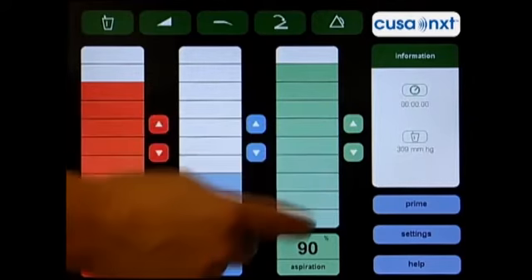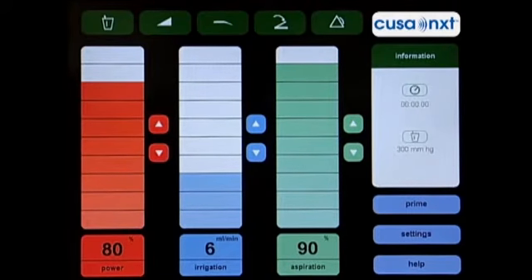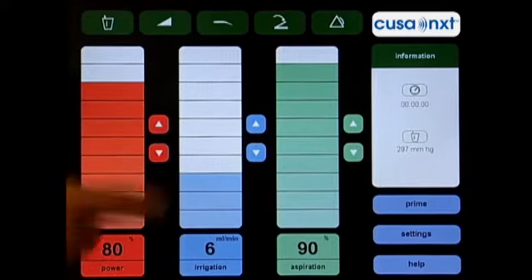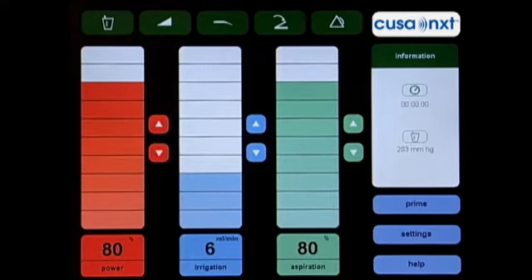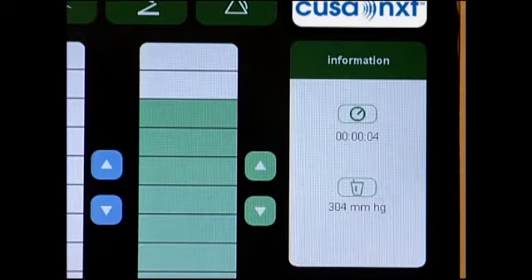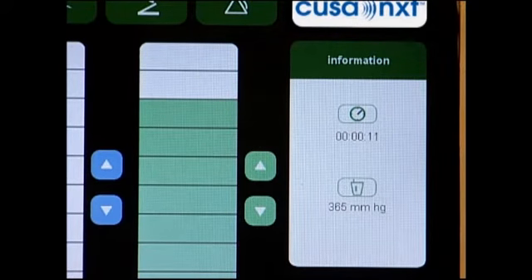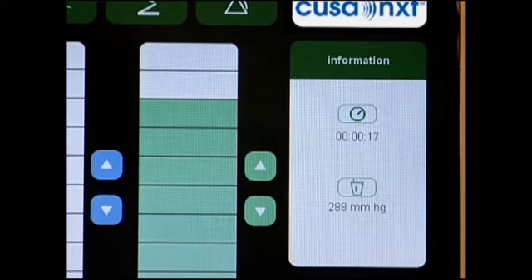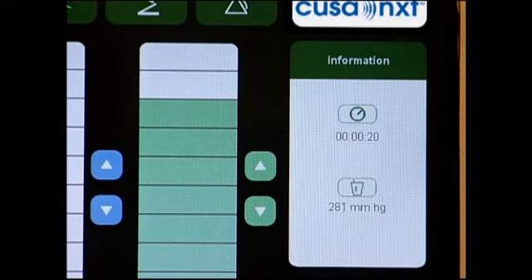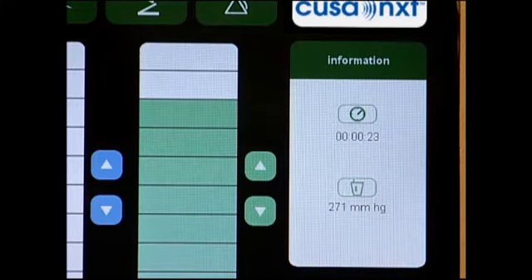To adjust the aspiration level, press the appropriate green arrows or indicator bar. Each touch of an arrow will increase or decrease suction power 5%. Touching the aspiration scale will increase or decrease the setting by 10%. Typical aspiration settings are between 70% and 100%. During system operation, the information panel will display the cumulative handpiece activation time and the actual suction power, measured in millimeters of mercury. Should the surgeon wish to change system settings, power, irrigation, and aspiration levels may be readjusted at any time during the operation by touching the appropriate scale or arrow.